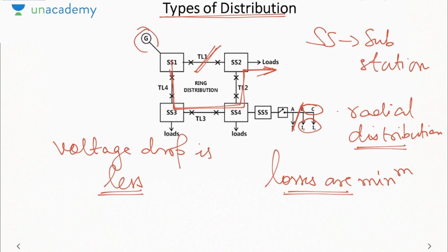But the disadvantage is, here to connect 4 substations we actually need 4 transmission lines. In case of radial, what would be the case? 1, then 2, then 3, then 4 - you only need 3 lines to connect 4 substations. So in ring distribution, the number of lines is more, meaning more losses as well as higher cost compared to radial. But that cost is compensated by the fact that it is more reliable than radial distribution.